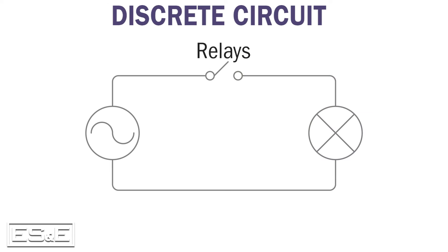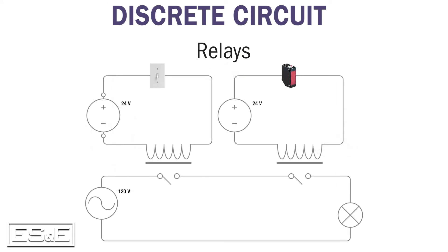From our original circuit drawing, we've replaced the switch with two relays. When voltage is applied to the relays, the circuit closes and allows power to be delivered to the light or the load. In the example, the power controlling the relay's coil does not match the load side of the relay's contacts. This allows the use of a safer voltage for the control circuit while providing larger power circuits to be switched on or off as needed.